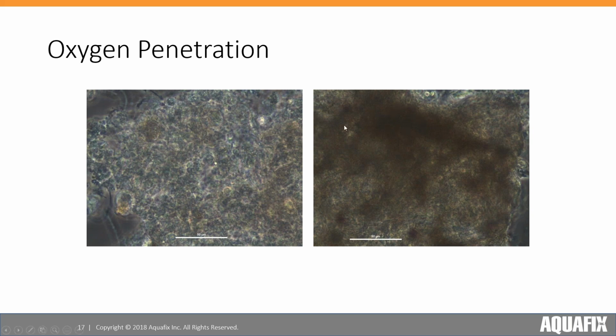So we're seeing quite a lot of dark areas compared to the normal light tan or yellowish sort of color that we normally see. So some issues with aeration is maybe the aerators got shut down due to a power failure or for some other reason. It is possible that there may be no good way for a plant to monitor aeration in their basins and adjust it quickly. That's unfortunate, and low DO can lead to anaerobic bacterial metabolism, generally within these darker areas.